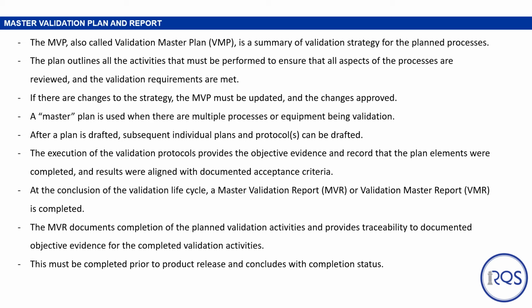After a plan is drafted, subsequent individual plans or protocols can then be drafted. So again, if there's more than one piece of equipment, you have the master validation plan, and then there would be subsequent individual plans and reports for each individual piece of equipment. The execution of validation protocols provides the objective evidence and record that the plan elements were completed and that results aligned with documented acceptance criteria. At the conclusion of the validation cycle, a master validation report, or again, validation master report, MVR or VMR, is completed. The MVR documents completion of the planned validation activities and provides traceability to documented objective evidence for the completed validation activities. This must be completed prior to the product being released and concludes the completion status.